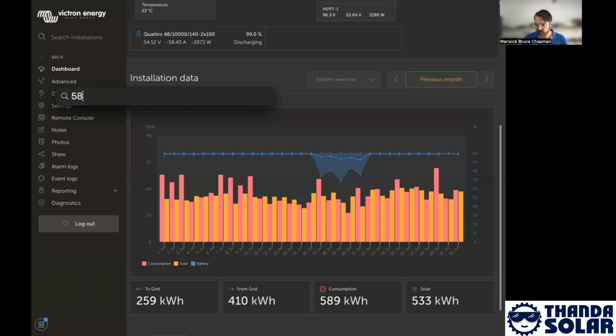So if we know that we have had 589 kilowatt hours of consumption, and we have generated 533 kilowatt hours of solar, then that means that we should have used 56 from the grid, all right? But if we subtract what we used from the grid, then we've got 95 kilowatt hours that have been lost, okay? And if we take that 95 kilowatt hours as a function of the production, then we're looking at a 18% loss. And it's an efficiency loss. It's a round trip efficiency. And what I'd like to talk today about is why that loss exists.